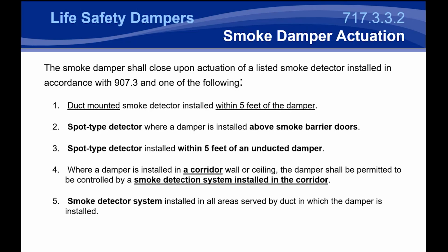Now, for tenant improvement, where there is nothing, you can certainly have those smoke detectors supplied with the damper. They don't have to be mounted with the damper. They can actually be mounted within 5 feet of a ducted damper or an unducted damper. And they really don't need to be installed on the damper coming from the factory. Now, that is a little bit of a labor savings, but there has to be clearance for these detectors and for the electronic connections that are going to be tying into the actuator and the temperature responsive devices for these dampers. Those connections do take up space on the sleeve.